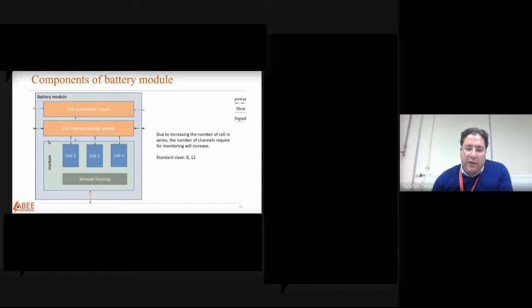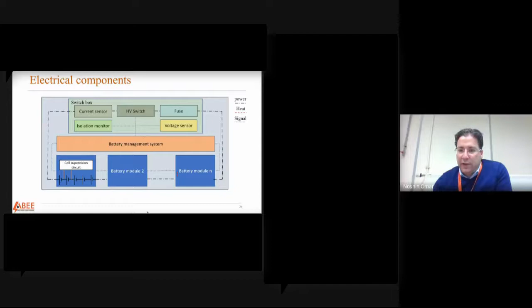Here, for illustration, you see the types of components we have: current sensors, high voltage switches, fuses, voltage sensors, temperature sensors, isolation monitoring systems, etc., that are typically part of a safe battery system design concept. This system is continuously interacting, monitoring, processing data, and giving the right actions accordingly. The battery management system, BMS, plays a key role—typically if this fails, the full battery pack will fail accordingly.